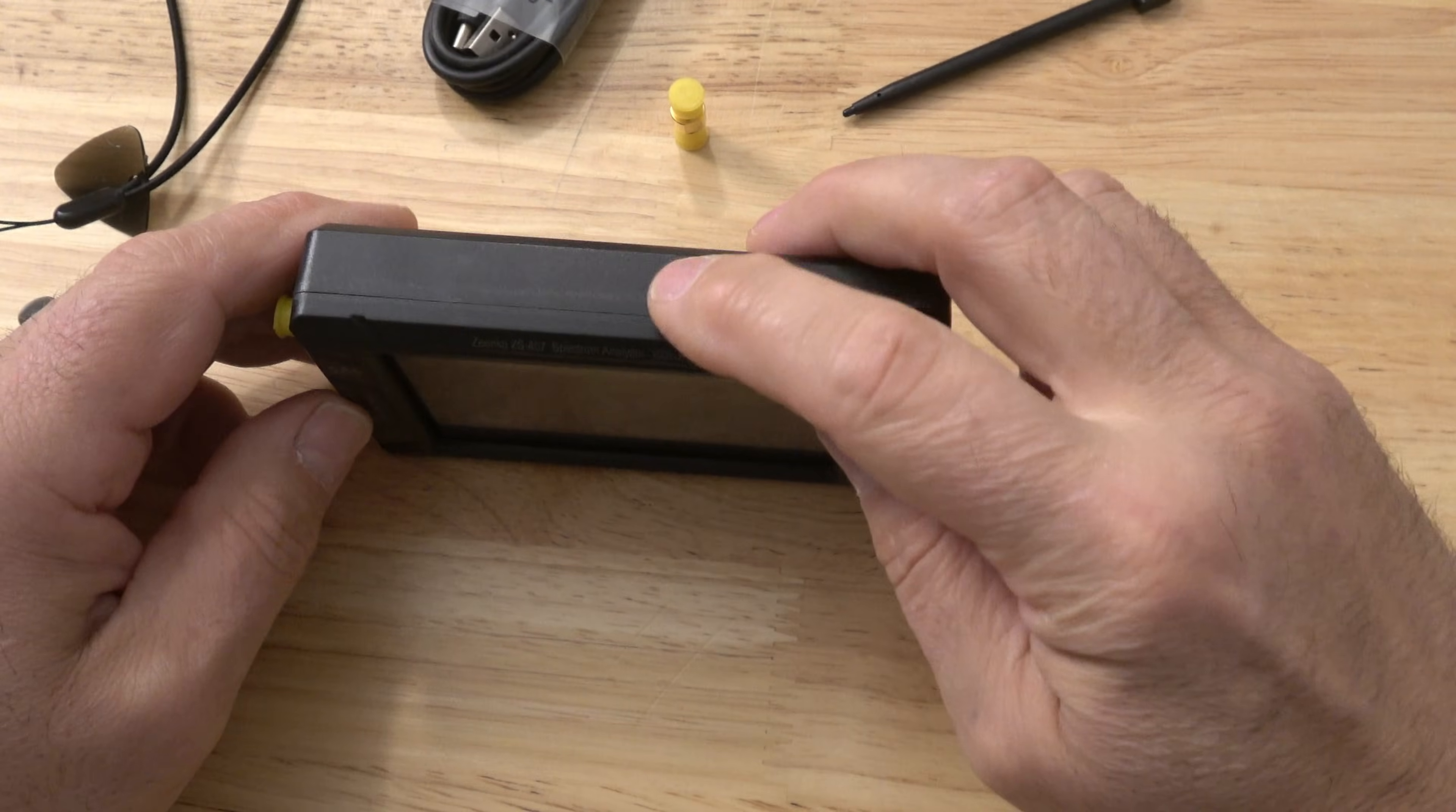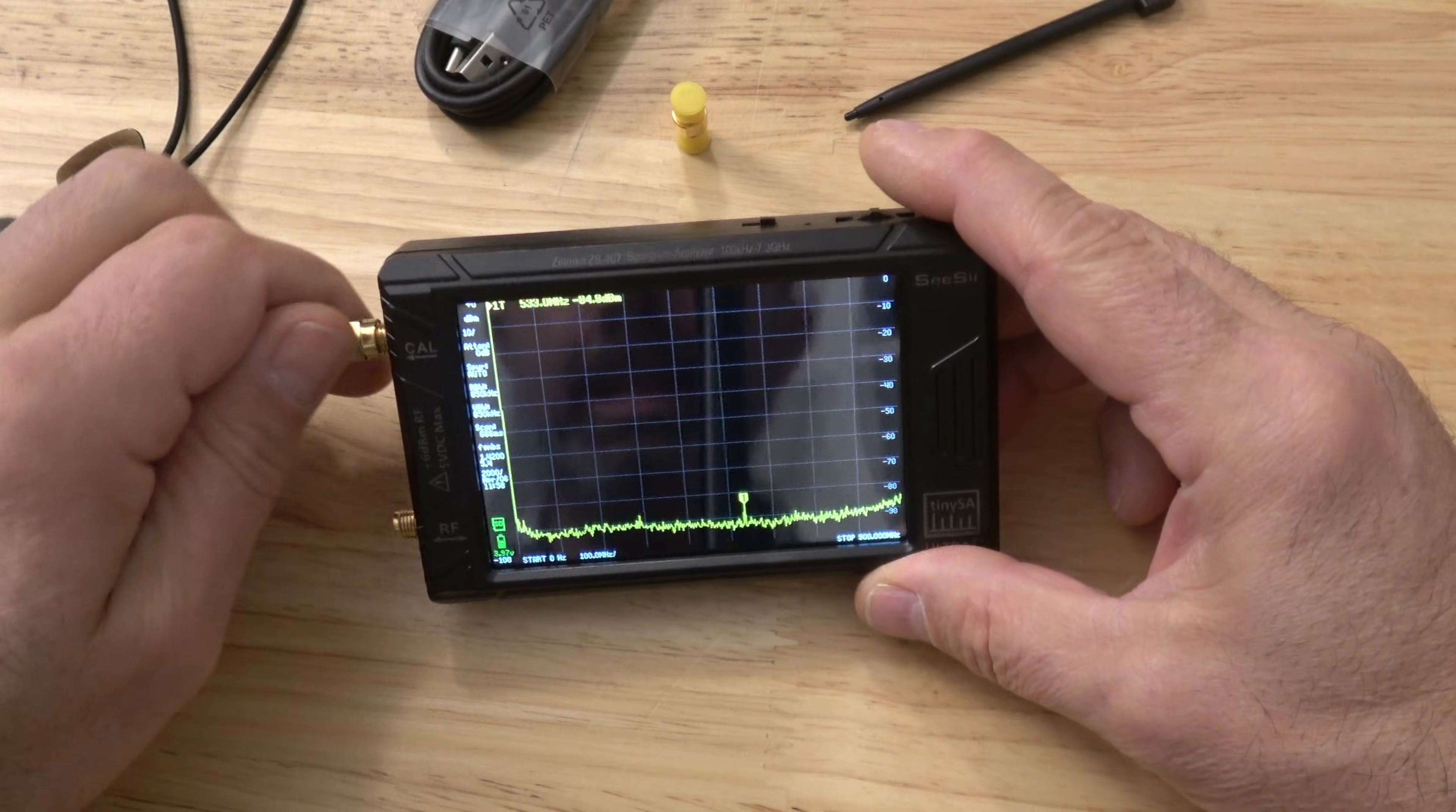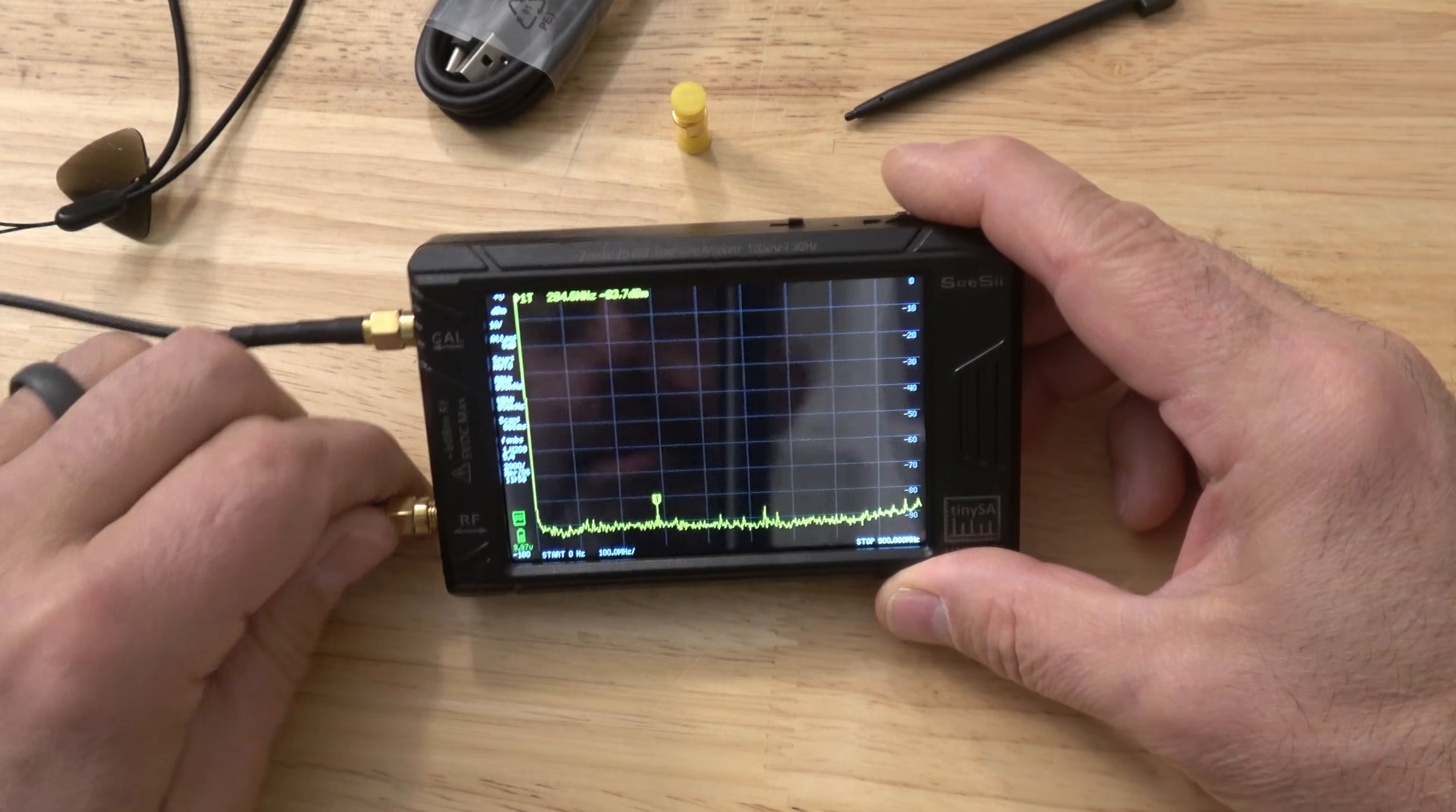All right. Well, here we are on the bench. Go ahead and turn it on. And it's very quick to boot, as you can see. And here we are. It's just checking out the noise floor. Now, it does recommend, before you do any kind of actual work with this thing, that you should do a self-calibration test. And to do that, we're just going to hook these cables together. And we're going to get into the menu system here.